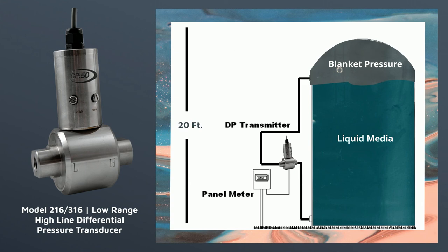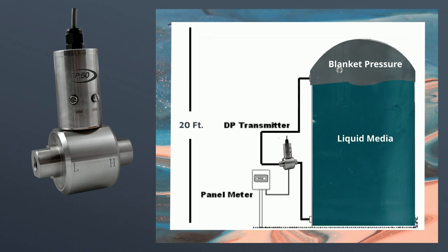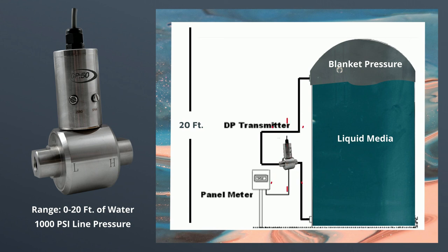The differential pressure transmitter will measure the gas blanket and liquid level on the high side. The low side will subtract out the gas blanket pressure. In the example shown you would need a differential pressure transmitter with a range of 0 to 20 feet of water and that can handle 1000 psi of line pressure. As the liquid level changes depth the transmitter will sense this, and if the gas blanket pressure changes it will also cancel out in your total head pressure readings.